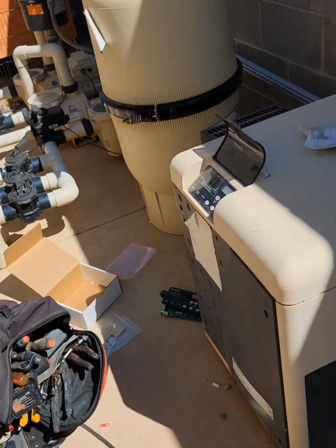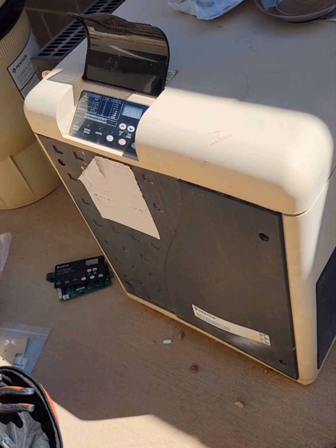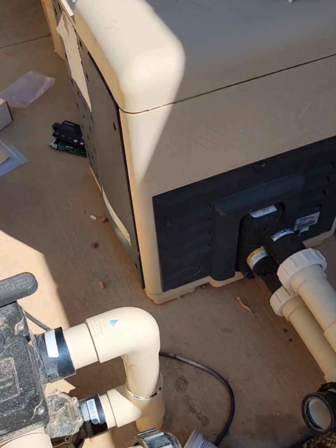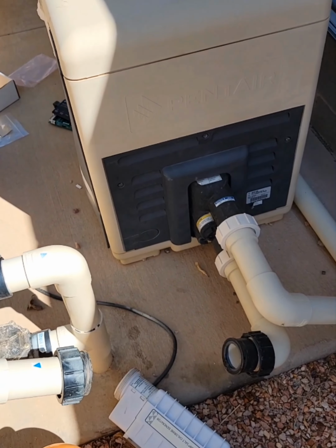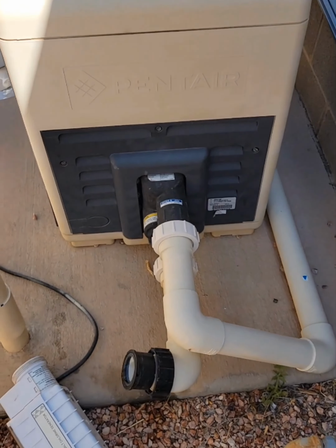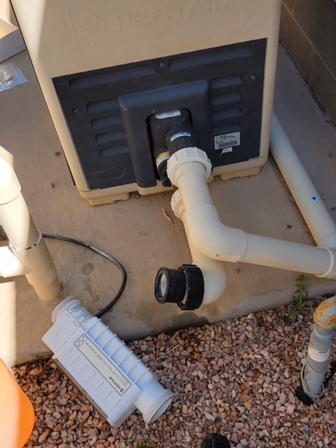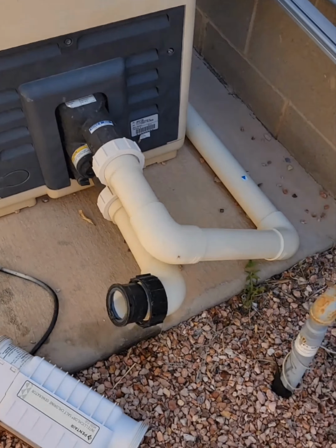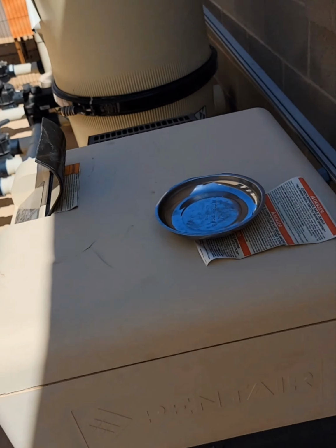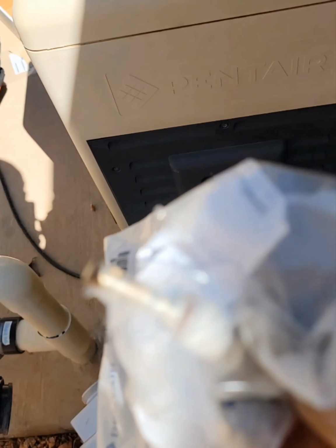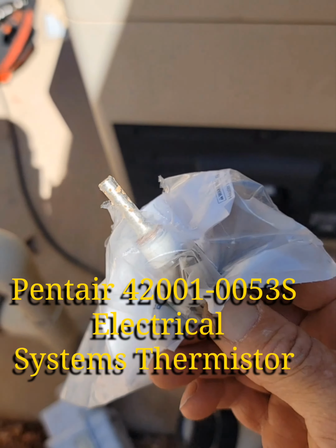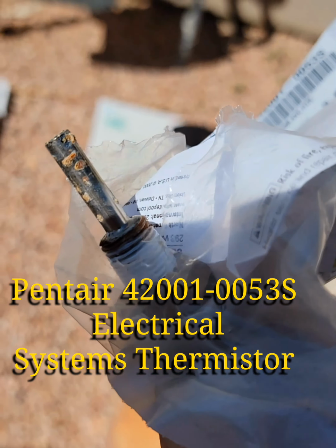So, after replacing the CPU and the keypad display, and getting the heater going, that worked. I then realized that I needed to replace the thermistor as well. It was giving me really crazy readings because we got really bad corrosion here on this probe, or deposits, corrosion, not exactly sure yet.